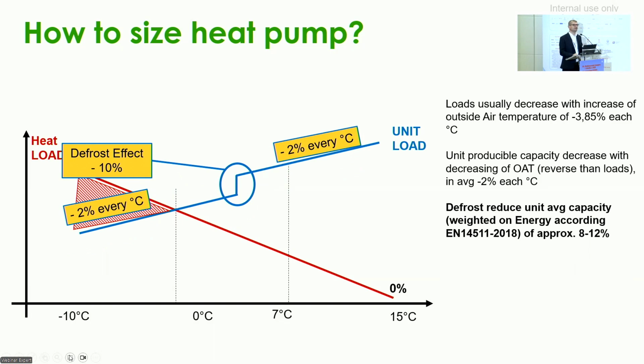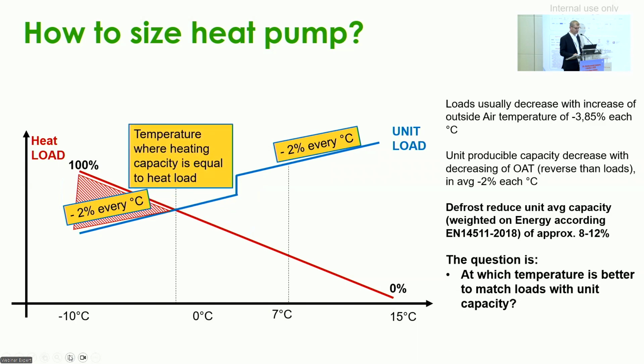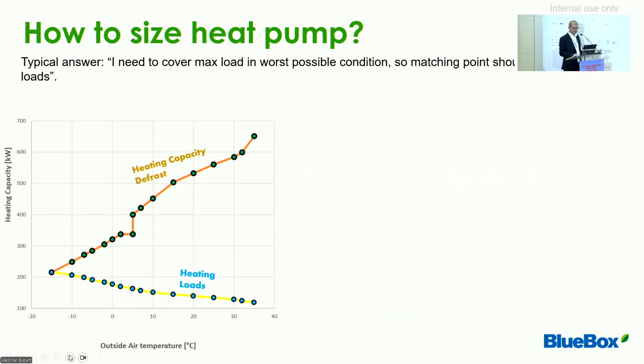Below a certain ambient temperature, the unit will periodically need to defrost. These graphs also give us another parameter: where the two lines cross, the heating capacity is equal to the load, meaning that below that temperature the capacity of the heat pump is not sufficient and we need an integration source. Above that figure, the heating capacity exceeds the load. This is called the bivalent temperature, and it is very important to select it properly, because if we take this example, you can see that the heating capacity, the orange line, meets the heating load at the lowest temperature. In other words, in the worst possible conditions.